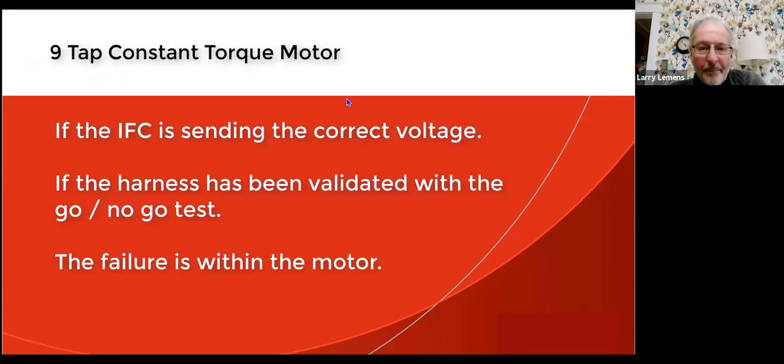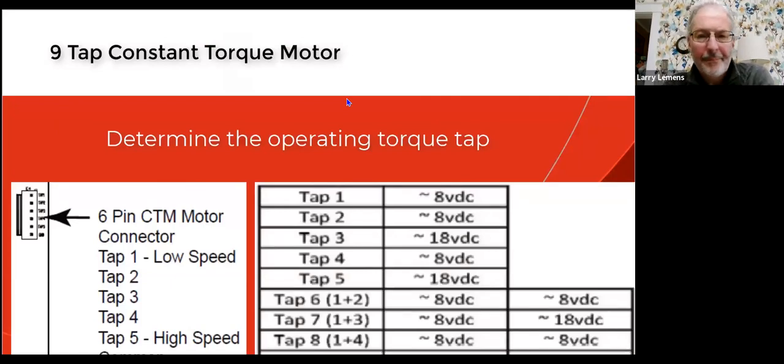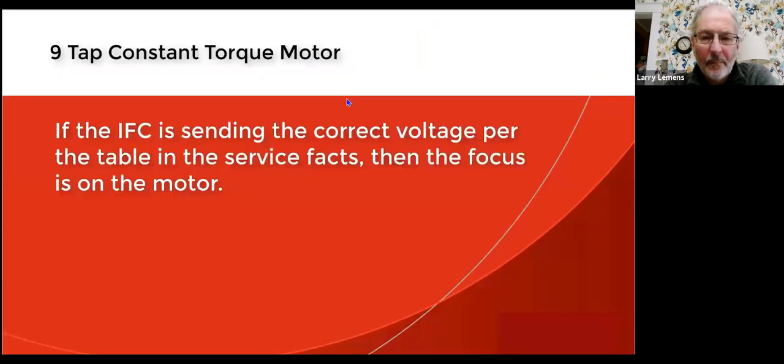If the meter confirms appropriate voltage and the motor is not running, since you've already done the 24-volt go/no-go test and know the wiring harness connections are solid, the issue is the motor itself. If the board isn't sending out the appropriate voltage, the IFC is to blame. Confirm what torque tap the IFC is showing and verify the voltage is representative of that tap per the service facts. For example, on torque tap seven: pin one still has about 8 volts DC, pin two has zero volts DC — wire two is not used for tap seven — and pin three actually has a higher voltage of 18 volts DC. Confirm the board is sending the right voltages on the right taps, and the motor should be running at that torque tap.